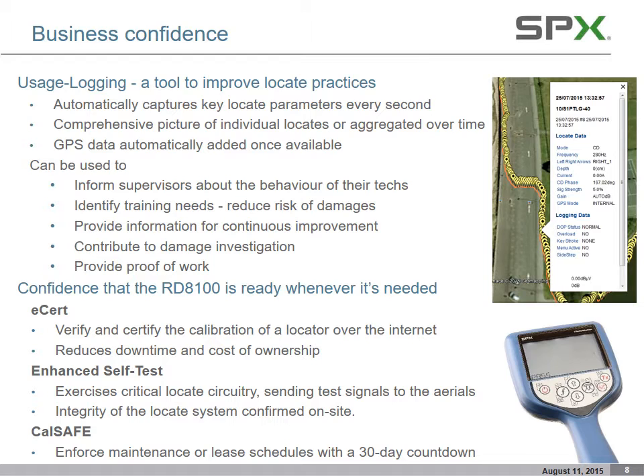That is something we saw in the RD400 in the 4000 series, and then on the 8000 series it was not on there. So now they've put the self-test back onto the unit. That doesn't take the place of the calibration checking, the eCert or the CalSafe calibration checking, but it does allow it to give you some kind of confirmation that the unit's electronics are possibly working just fine.